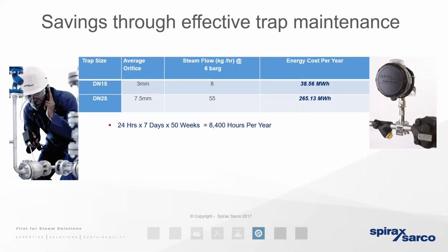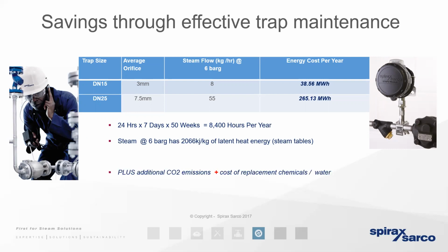So if we know the size of the steam trap and therefore the size of the hole in the trap itself, if we know the steam distribution pressure, if we know the operational hours per year, then we're able to determine the loss of energy that is going to reflect to the steam using client. So if you consider a failure rate of 1 in 10 seems to be the average. If a client's got 1,000 traps or even 100 traps on site, a failure rate of 1 in 10 can represent a significant loss of energy over a financial year. And if our client knows their cost of steam, well, the calculation's an easy one.